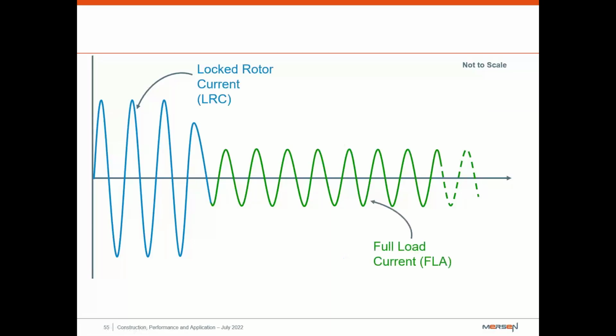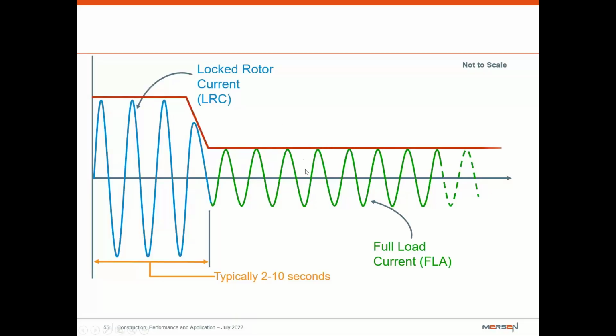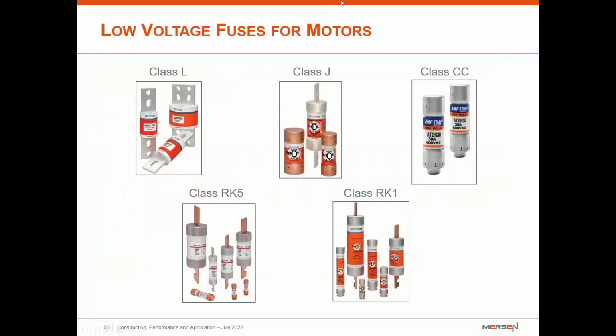So this is from a motor when it has the locked rotor current, where it's actually stopped, and how much energy it takes to start it. Once it starts, the inrush current is going to peak pretty high for about 2 to 10 seconds before it comes into normal operation, or the full load amps. What we want is a fuse that is not going to necessarily open during the locked rotor current part of this. It's going to wait until the full load, and then if there is any kind of an issue, you want your fuse to open. The different types of fuses that we offer for motors are our Ls, Js, CCs, RK5s, and RK1s.